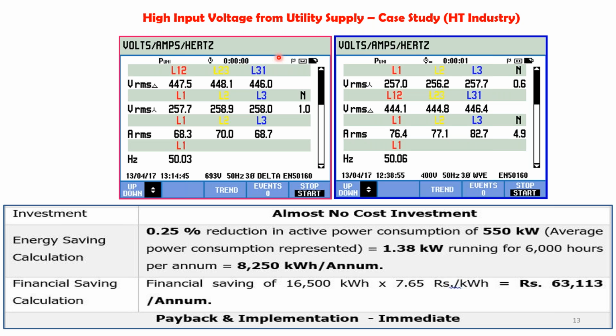So therefore, we suggested a simple idea: adjust the voltage. Of course, this industry has a transformer, and the transformer also has an OLTC, on-load tap changer, RTCC. But one important point is the OLTC is not working, and it went for service in the past. During the audit time, before 6 months back, it went for problem rectification. So therefore, they bypassed the OLTC and RTCC. They are operating with the normal voltage supplied by the utility company. So we suggested to kindly replace or retrofit your OLTC system, and you can maintain the voltage within the specified limit.